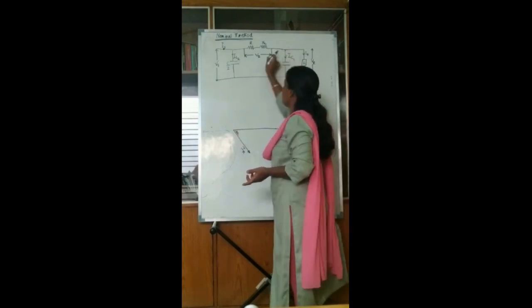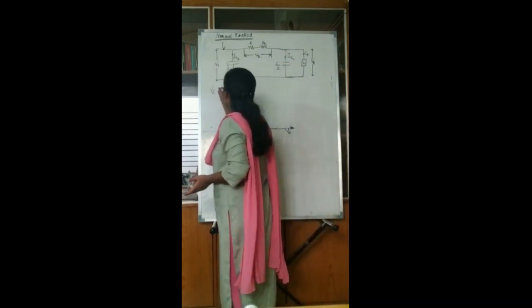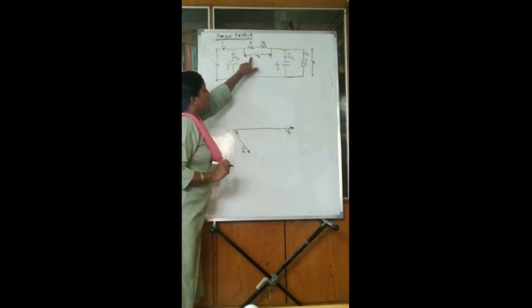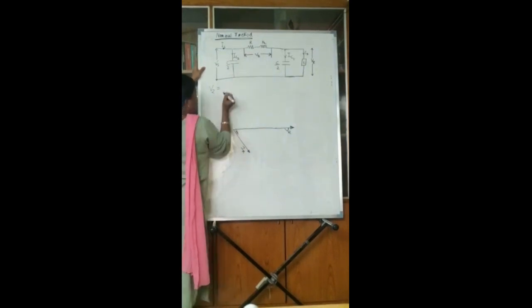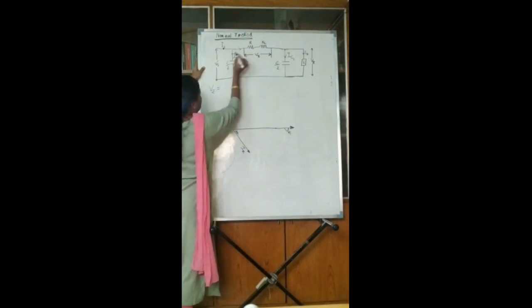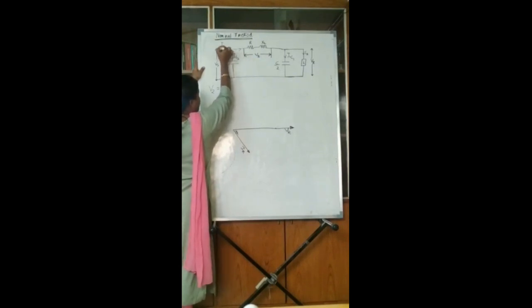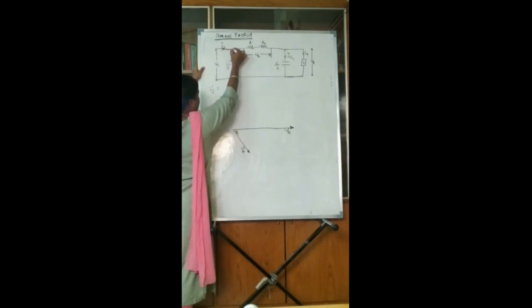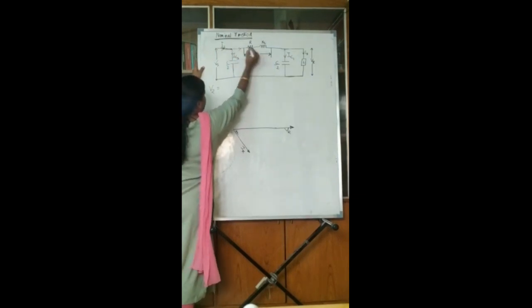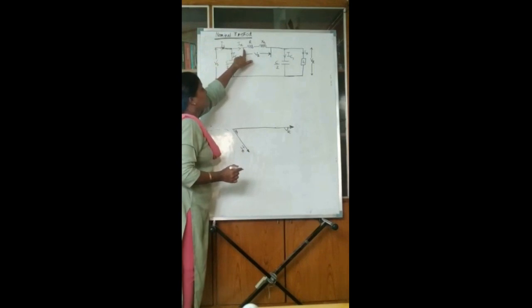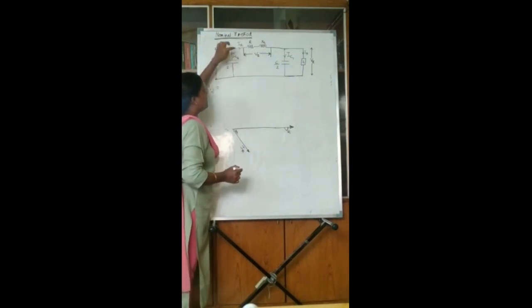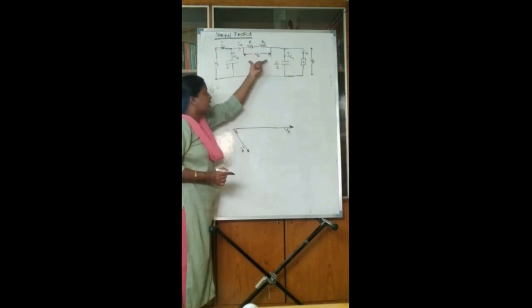After knowing Vr, let us find Vz. Vz is equal to the voltage across the resistance plus the voltage across the inductance. To find the voltage across the inductance, I first need to know the current flowing through the impedance. That current is Iz — this same current is not Ir, because at the sending end the current Is is divided. The current flowing through resistance and inductance is Iz, and Iz into R plus Iz into XL gives us Vz.